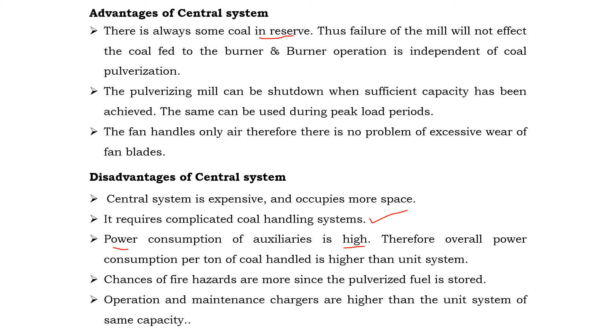We also have disadvantages of using the central bin system. The central system is expensive and occupies more space. It requires a complicated coal handling system. The power consumption of auxiliaries is high. Therefore, overall power consumption per ton of coal handled is higher than the unit system. Next disadvantage, chances of fire hazards are more since the pulverized fuel is stored. Last one, operation and maintenance charges are higher than the unit system of the same capacity.